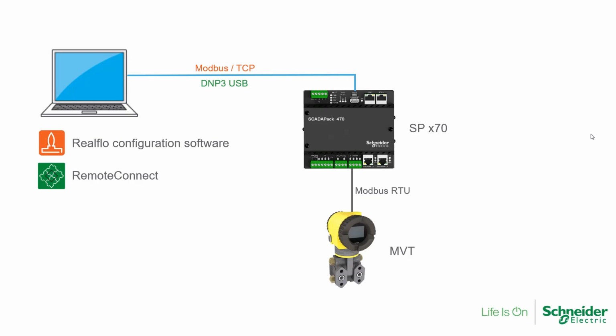Well, how is it possible that we have both Modbus TCP over USB? Well, the USB port on a 470 is actually using IP over USB. It does this by assigning an IP address to that USB port. This is its default internal address of 10.2.3.4. And the driver automatically assigns a compatible IP address at your PC. So let's try the USB connection in this quick start guide.